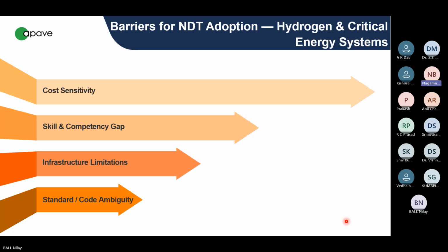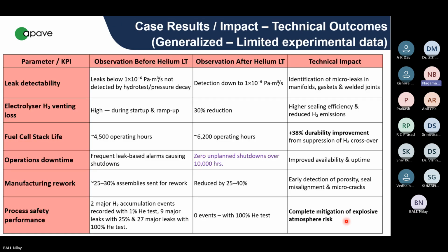If I may ask a question here, Nilay: when you say observation after helium leak test, you are implying that after the leak test, things have been fixed, and therefore this has come down. Is that what it means? Correct. In operation downtime, you do not have any unplanned shutdowns for 10,000 hours. Planned shutdowns will have to be done, but no unplanned ones before 10,000 hours.